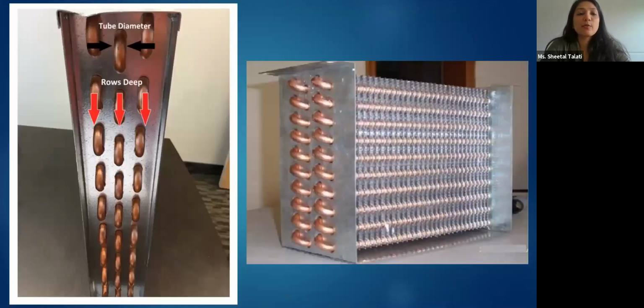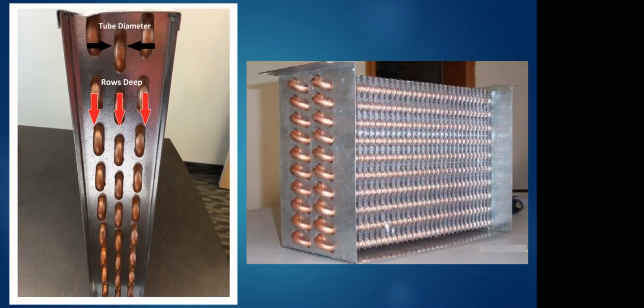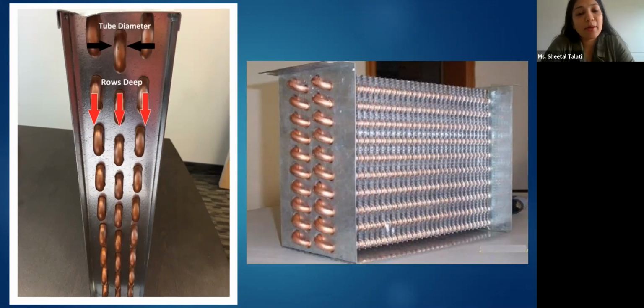Now, this is a very interesting part where we ask what is the number of rows of the coil. Many people get confused and count the number of U-bends attached. So they'll say 28, 25. No, this is a 3-row coil. The first picture shows a 3-row coil. This is how you measure. You go vertically, 1, 2, 3. Is everybody there with me? Yes, right here. Okay, looking at the second image, can you tell me how many rows the coil is? Tricky one. It's a 4-row coil. So you have to measure it vertically. You go downwards as the arrow is shown. Similarly, this is a 3-row coil and the second one is a 4-row coil.